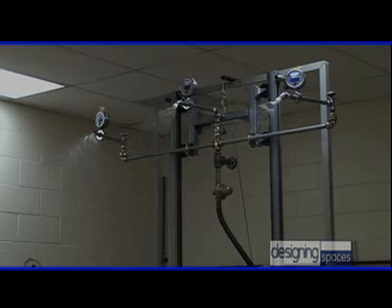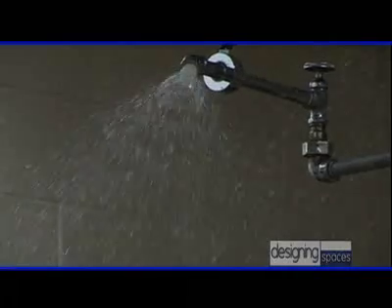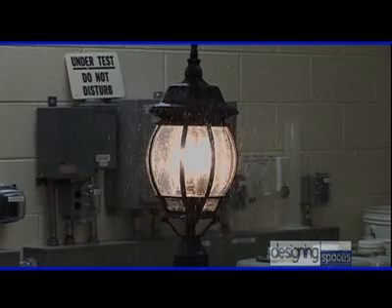Ted, many products are used outdoors. We have to assume that they're going to get into a rainstorm sometime. We have to test for it. So what we're doing here is turning water on a product like this lamppost and making sure that it doesn't get wet inside. Once it's done with the rain, we open it up, and if there's a drop of water on anything electrical, it fails the test. I've never been accused of being a genius, but I do know this. Water and electricity do not mix.